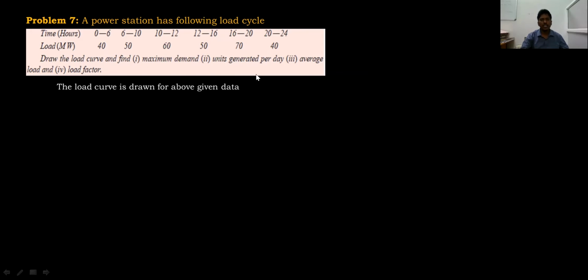From the load curve, how can we find units generated? The area under the load curve itself gives the number of units generated per day, because the x-axis is time and the y-axis is megawatts. Megawatts into hours is the area under the load curve, in megawatt hours, which we can convert to kilowatt hours, which equals units generated per day. The total area under the curve divided by 24 gives you the average load, as well as the load factor.